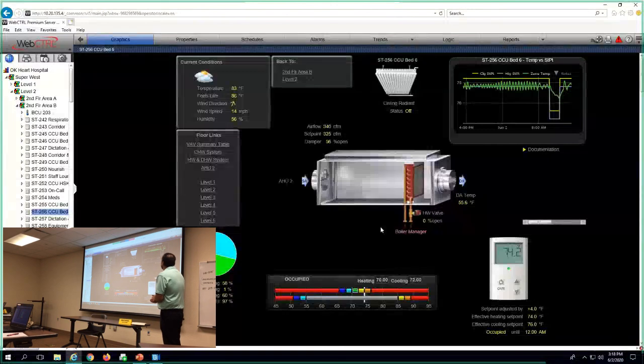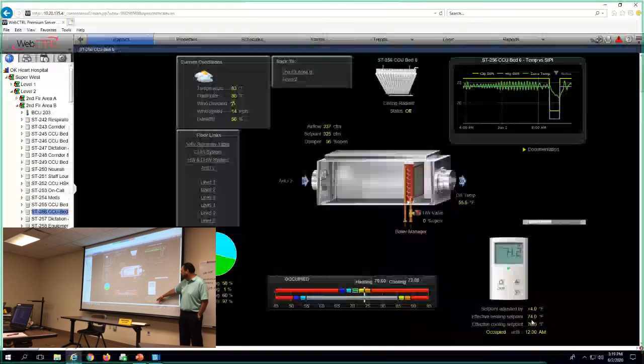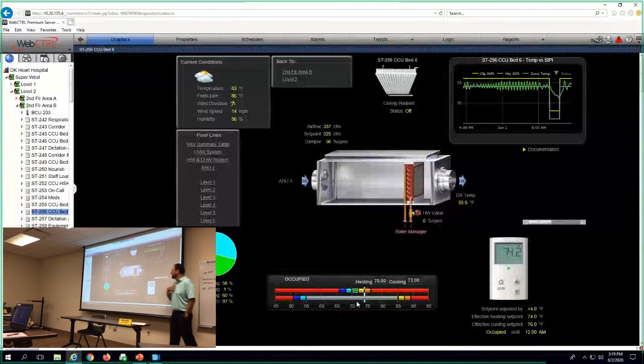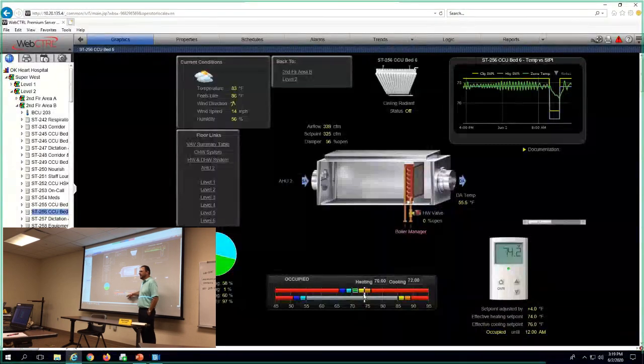All right. So no other questions on the colors? So here's where the colors come from. If you look at this down in the green box, this space, we are in CCU bed 6. The heating set point is 70, the cooling set point is 72. But look here. The occupant has got the space adjusted up 4 degrees. So that automatically made our heating set point 74 and our cooling set point 76. If I was to look at this and say, Michael, you just lied to us, because you said a while ago that if the temperature's in between those two spots, then it's going to show up green.